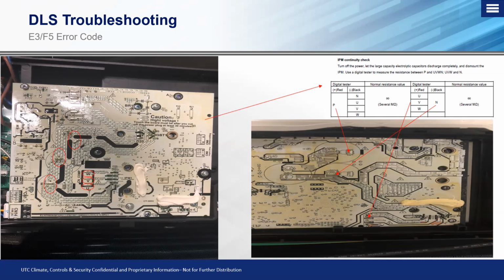So you'll see on here, this is typically how we do an IPM continuity check to make sure that nothing has failed internally between the capacitor buses all the way up to the U, V, and W terminals. In this particular circumstance, I have highlighted the compressor terminals W, V, and U, which is how we check that. You can also do the same exact process on your capacitor buses, which we see here highlighted in red. They'll have a positive and a negative post on them.